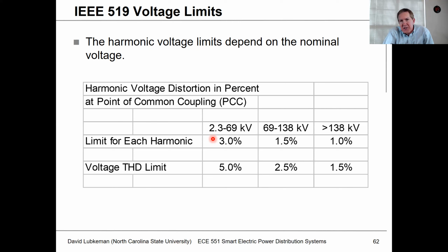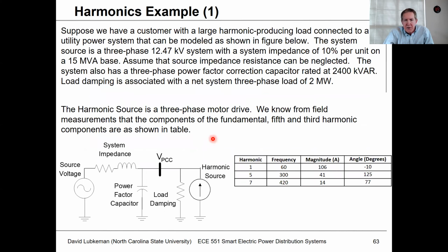And so this is something you may have to address on certain industrial circuits with a lot of harmonic producing loads. So anyway, this is just a final example that shows some of the number crunching you may need to do. I've got this little system here to the left with the power factor correction capacitor, 2400 kVAR, and it's got a resistive load of 2 megawatts. And so we're going to use this to get an equivalent C, R, and L.